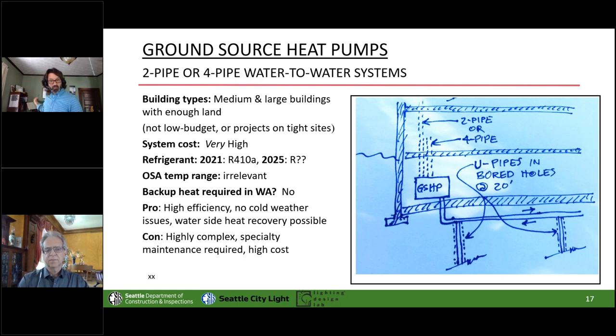What's neat is once you've got that well field, you can do a water to water heat pump and go two pipe or four pipe. You can go water to air heat pumps, also known as water source heat pumps, and just do a distributed loop around your building of that ground source loop water and do those individual distributed ones. You can go to VRF systems. There are water cooled condensers for VRF. So if you want zone on zone on zone, you can have that with VRF with that level of flexibility. And they're all highly efficient.